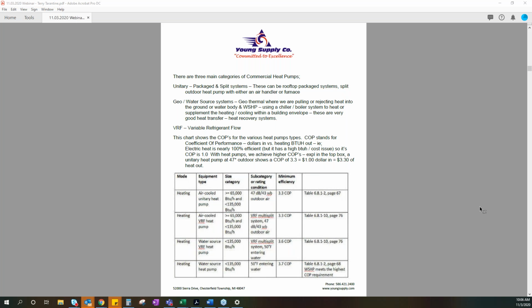And if we look at the chart below, we're talking about some COPs. COP is basically just coefficient of performance. I have a little explanation there, but I'll go over it. It's all kind of based on electric heat. Electric heat, for all practical purposes, is 100% efficient. It just costs a lot per BTU. So electric heat COP is 1. You put in $1 of cost, you get out $1 worth of heat. We're going to talk a lot about heat with heat pumps, more because we know we have enough cooling capacity. We're really designing towards heat. Talk a little bit more about that as well.